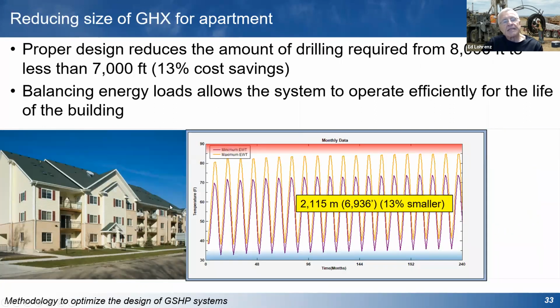The apartment building, because of the amount of energy that you're trying to shove into the ground versus how much you're taking out, you can actually reduce the size of the ground heat exchanger from 8,000 feet to 7,000 feet, reducing the cost of the system, and it's going to operate for the life of the building within that temperature range.